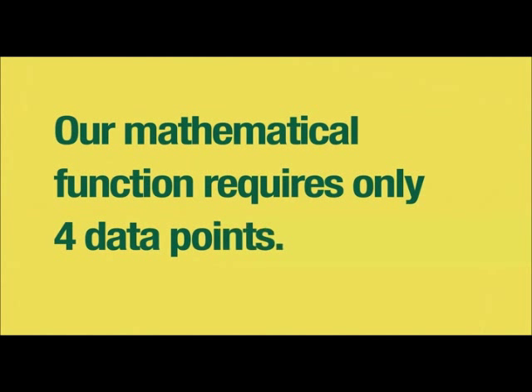Actually, as few as three data points are absolutely necessary. But to leave room to spot errors, you can add one. So four data points, hence four pieces of film. So with FilmQA Pro 3.0 and fewer data points, this original calibration takes less material, less of your time, and it's just once for each lot.